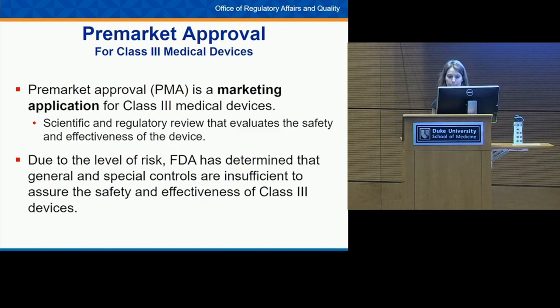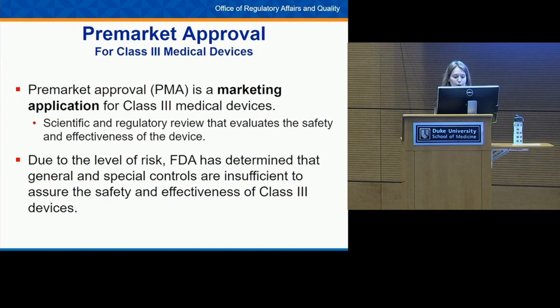For Class III medical devices, all new devices require pre-market approval (PMA) before going on the market. PMA is an independent review by FDA to assure safety and effectiveness — it's the most stringent type of marketing application, often compared to an NDA or BLA for drugs. Because Class III devices are so high-risk, general and special controls are not sufficient; you really need to prove safety and effectiveness through this PMA application.